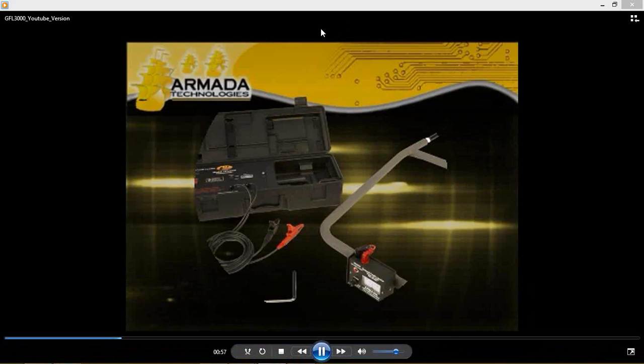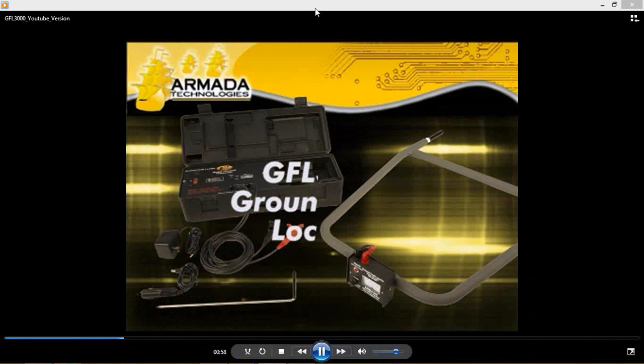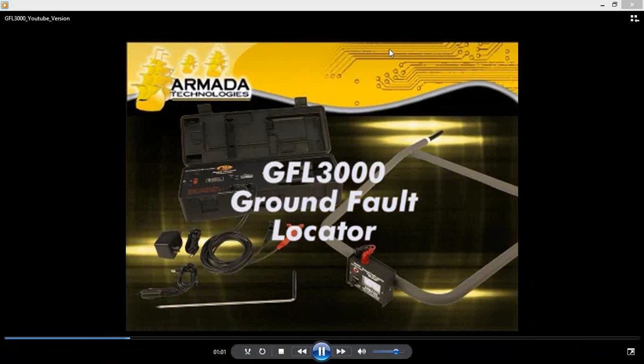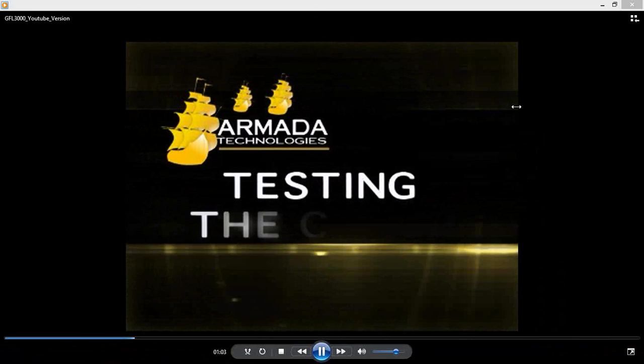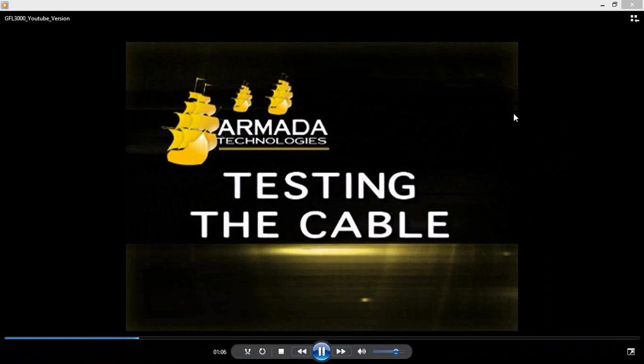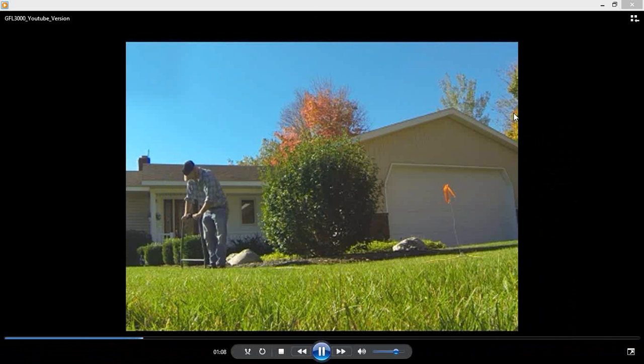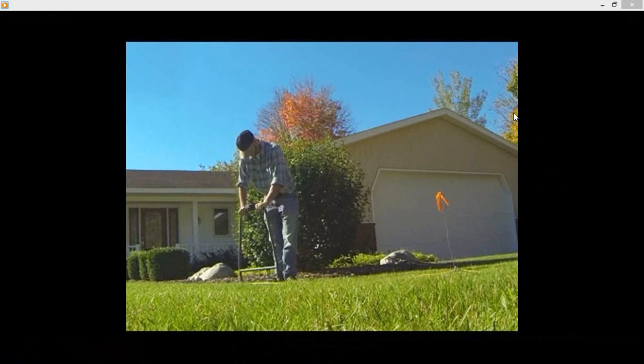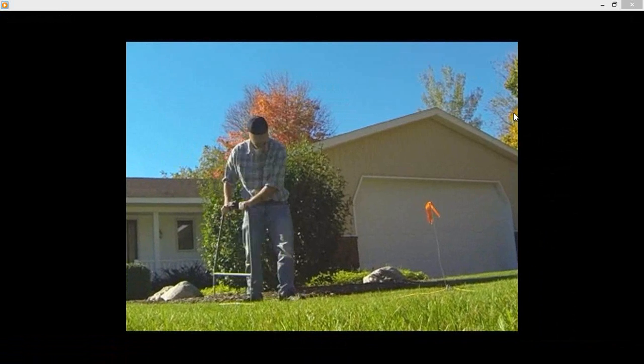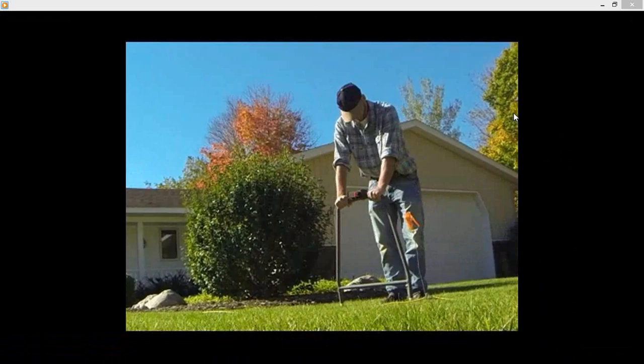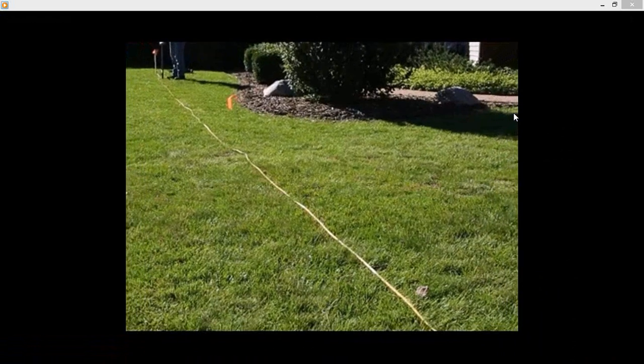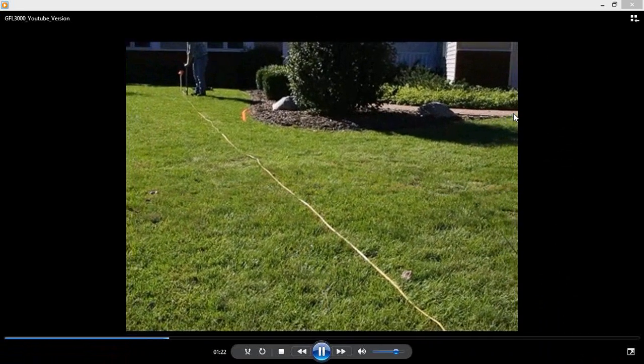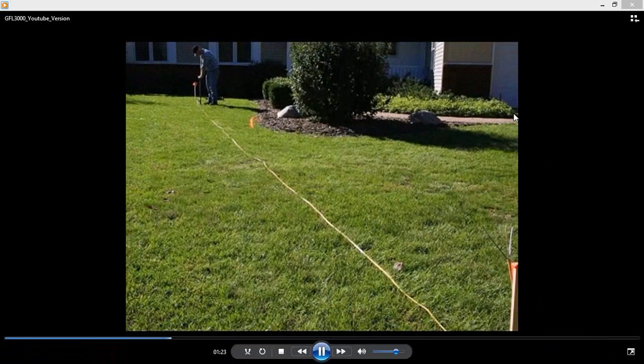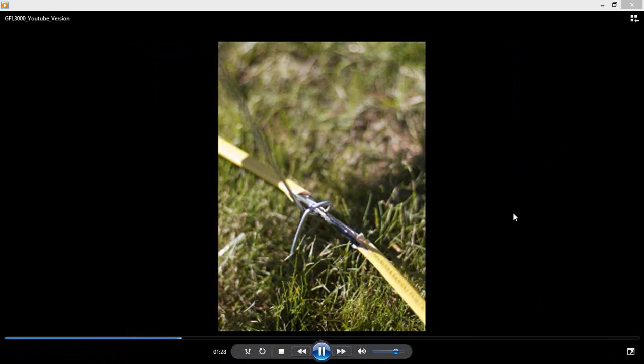We will demonstrate this process using the Armada Technologies GFL 3000 Ground Fault Locator. The GFL 3000 is designed to pinpoint the exact location of a ground fault in a cable. The GFL 3000 is not intended to locate the entire path of a cable. To effectively pinpoint the location of a fault using the GFL 3000, the path of the cable must be previously determined and the wire must be in direct contact with the earth.